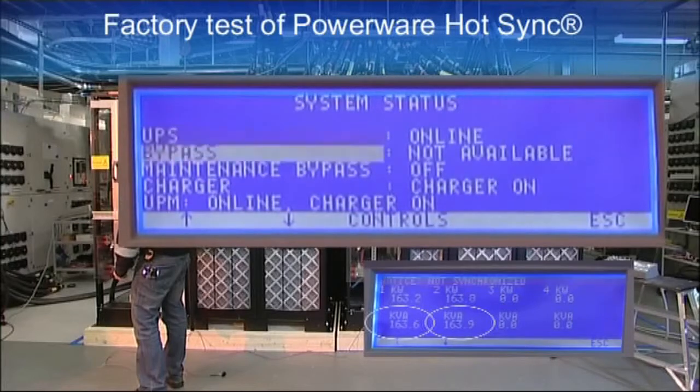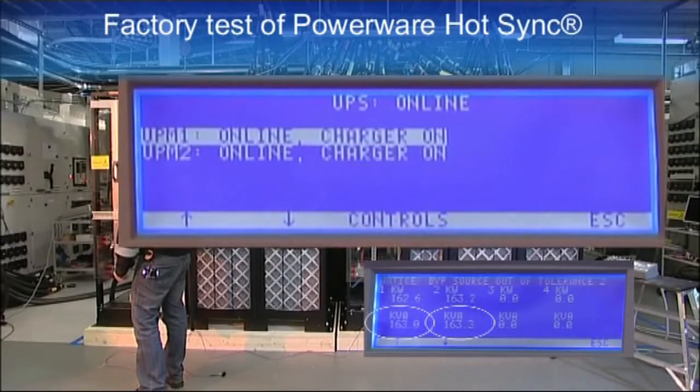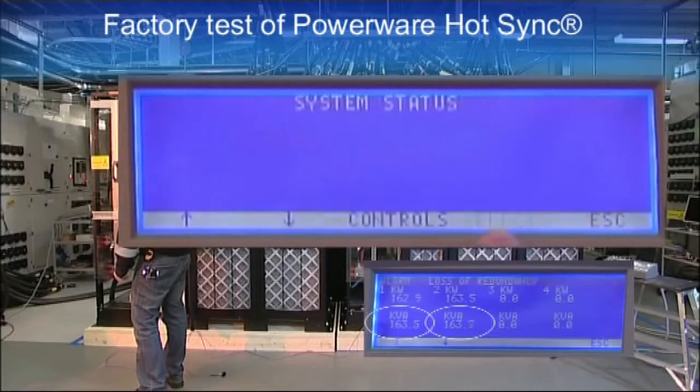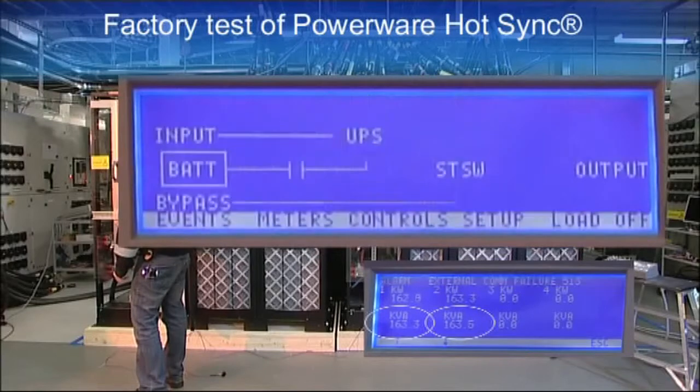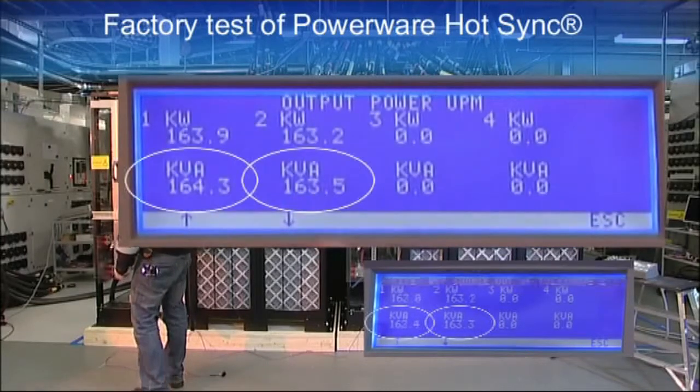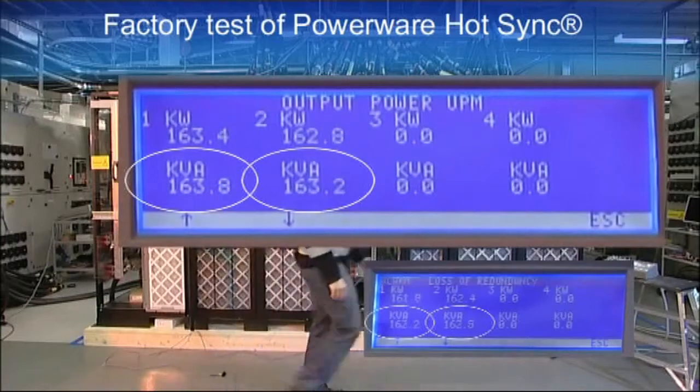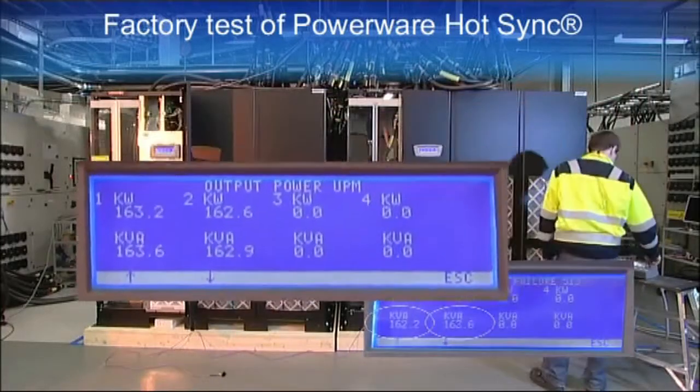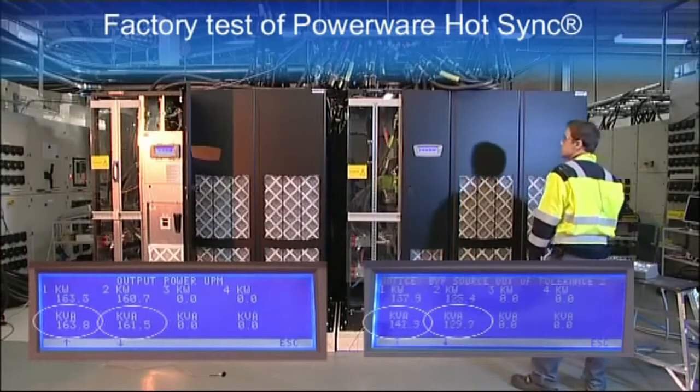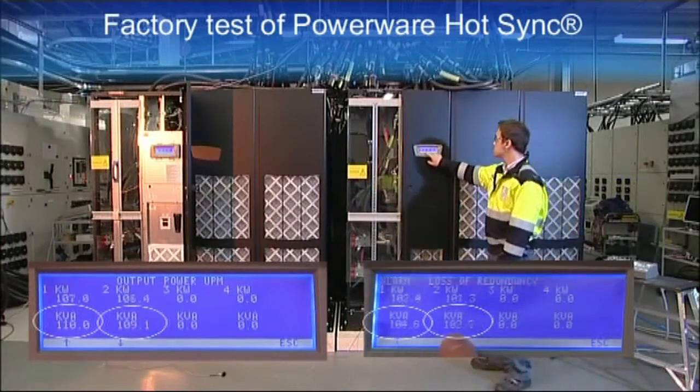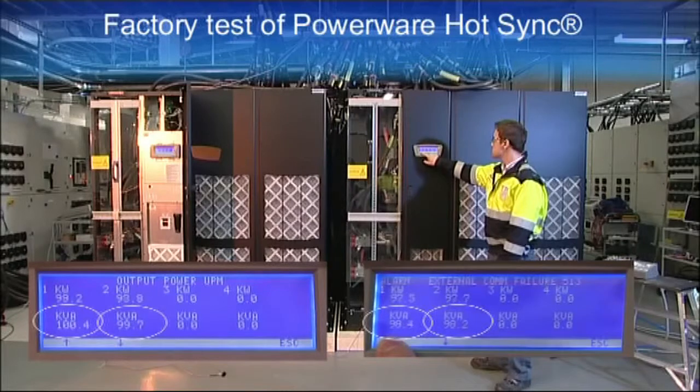UPS won't allow shutting down a power module because the alarm is active. The system has redundancy, but without communication, UPSs don't know it. The load level is decreased to the original 100 kilowatts per UPM level and loss of redundancy clears.